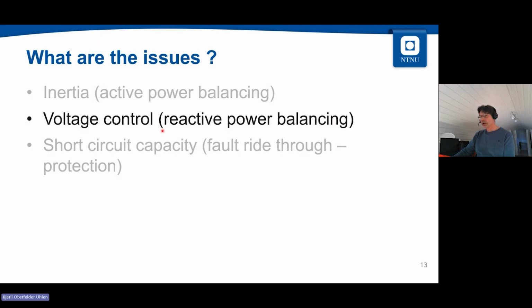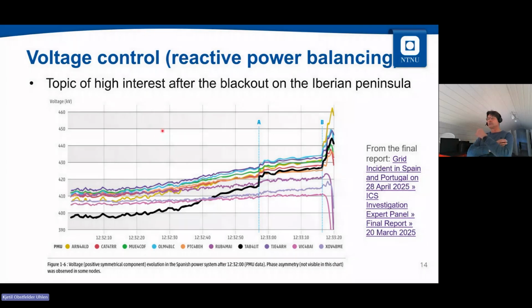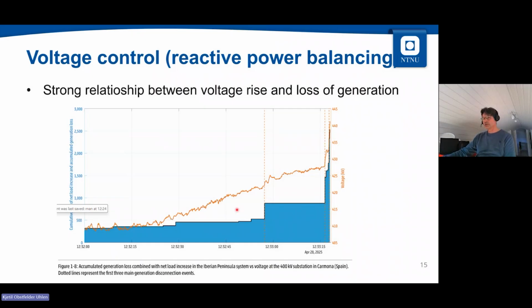Stepping to voltage control, the reactive power balance—this is a topic that has gained a lot of interest after the blackout in Spain and Portugal, where voltages came out of control in a way, and a lot of generation was stripped due to that, and it ended up in a collapse. You could see, from the final report on that event, the relationship between voltage rise and loss of generation, which is an uncommon way to look at it, but it signifies the need to control voltages.